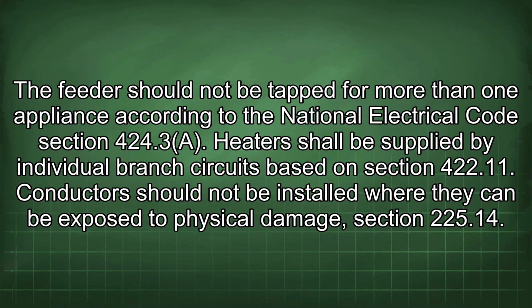A feeder should not be tapped for more than one appliance, according to the National Electrical Code Section 424.3a. Heaters shall be supplied by individual branch circuits based on Section 422.11. Conductors should not be installed where they can be exposed to physical damage, Section 225.14.